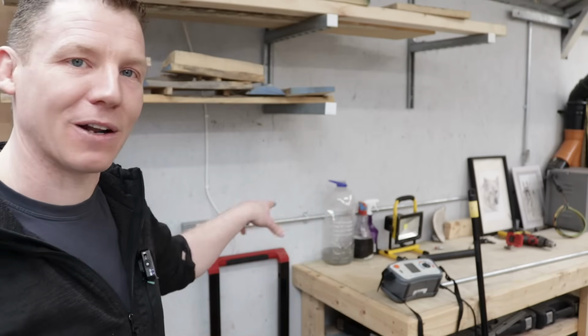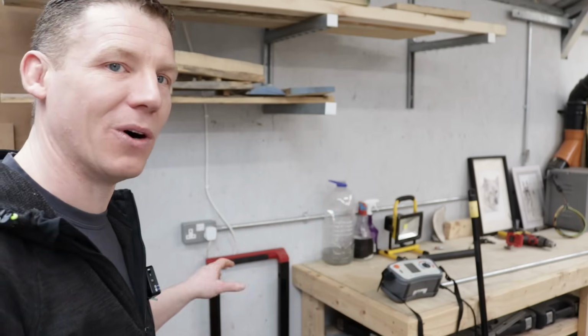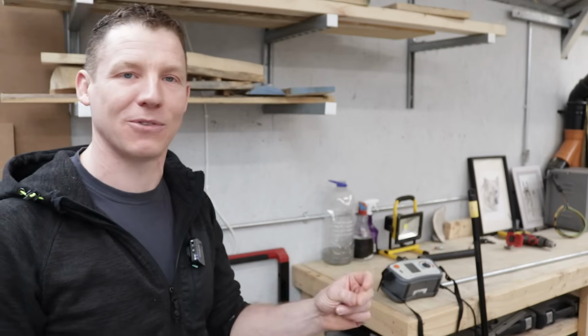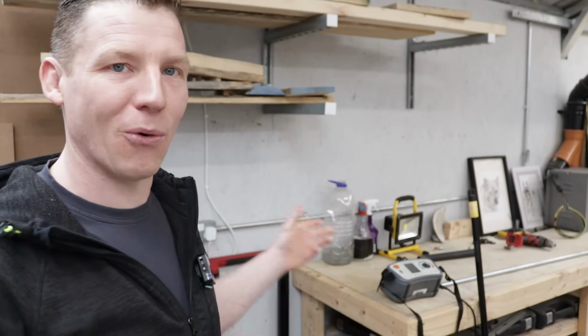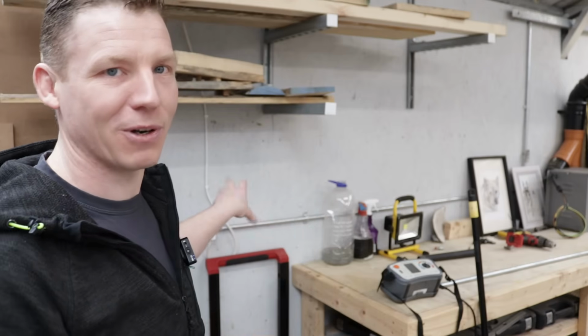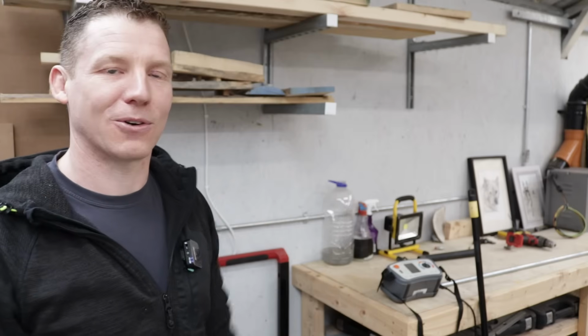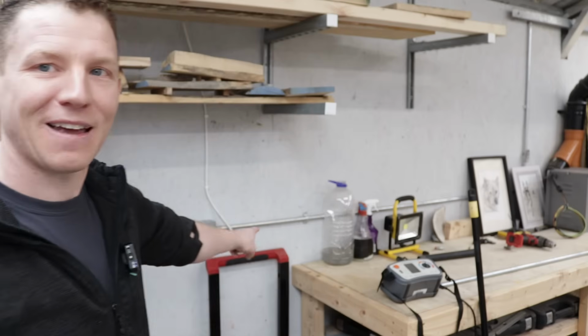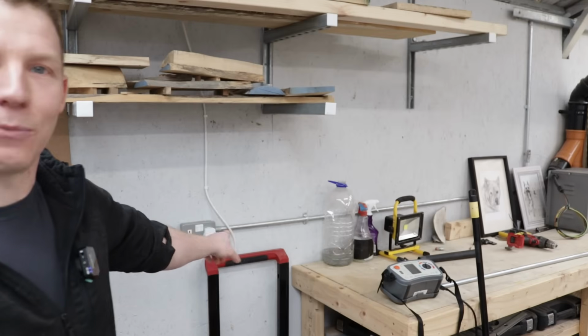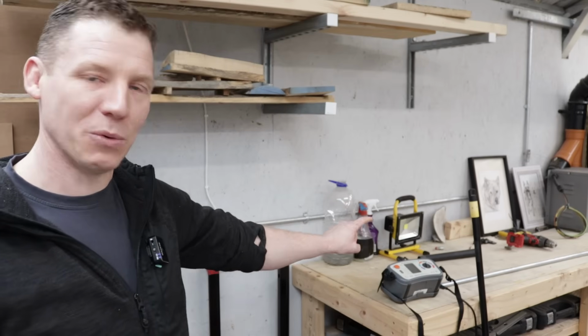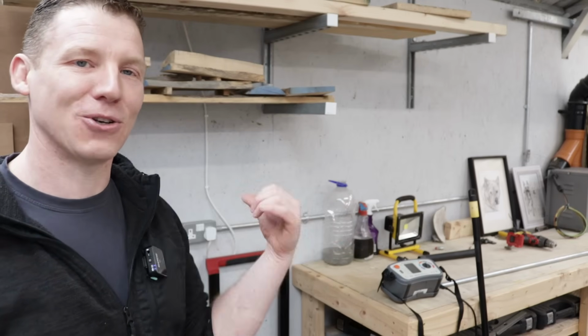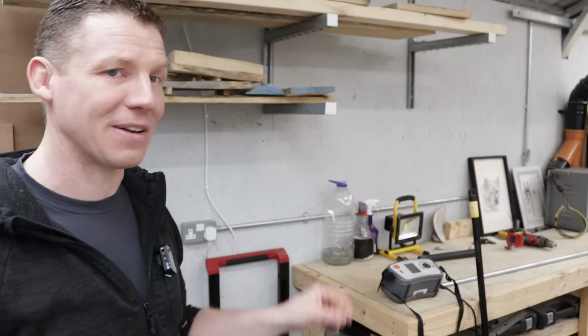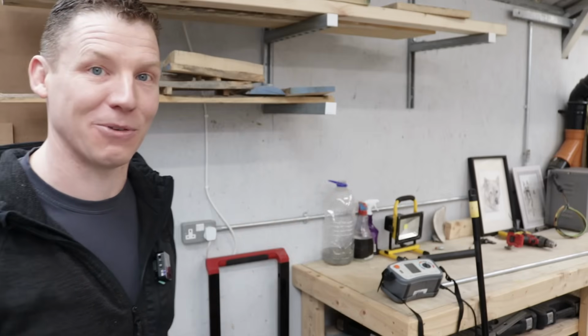My sockets are on a 20 amp breaker, so I need 60 to 100 amps to flow in an instant to blow out the trip switch for my socket circuit, to ensure that I don't turn my socket circuit into a heating coil. So let's test the loop impedance here now, and we can test the short circuit current that we would get on short circuit with the meter. I'll show you that, and then we'll add the extension lead and I'll show you that, and let's have a look at what difference it makes.